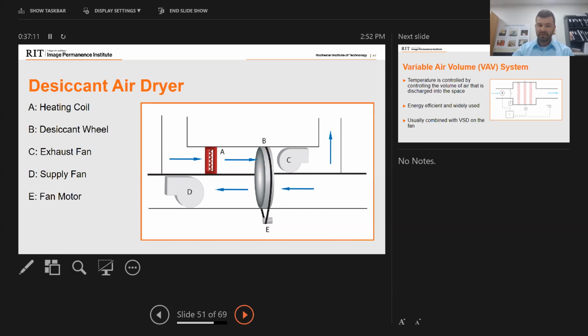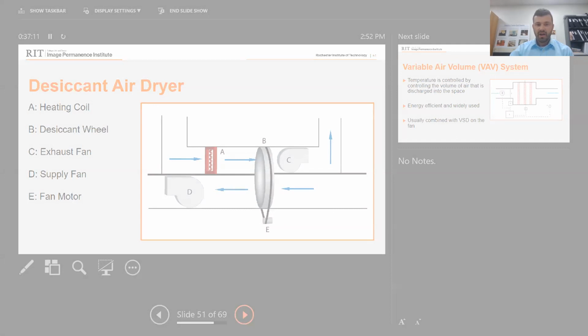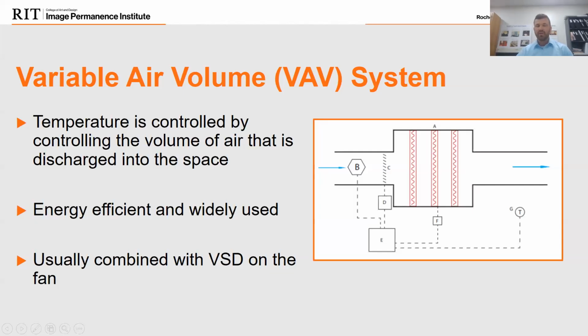Just before you move too far past the desiccant wheel, can that be added to an old system? Their system is from the 60s and they're told there's no option for HR. So there was a question, can a desiccant wheel be added to an older system? And the answer is, it depends on the system you have. Some older systems may not be able to have a desiccant added to it. Some can. It really depends on the type of system. You'd want to work with a mechanical engineer to ask them that.